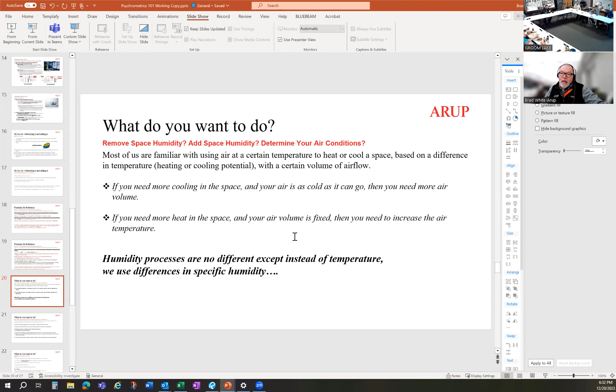Likewise with moisture, if you've got an air off a cooling coil at a certain absolute humidity rate, a certain number of grains per pound, and you want to dehumidify a space with a lot of people in it, you're going to have to add either a lot more air or take the same amount of air and dry it down to a lower grains per pound. So you've got a greater delta. It's like delta T, delta temperature for heat, delta grains for humidity. It's the same process. You're moving mass of air through a space at a difference in humidity and or temperature.